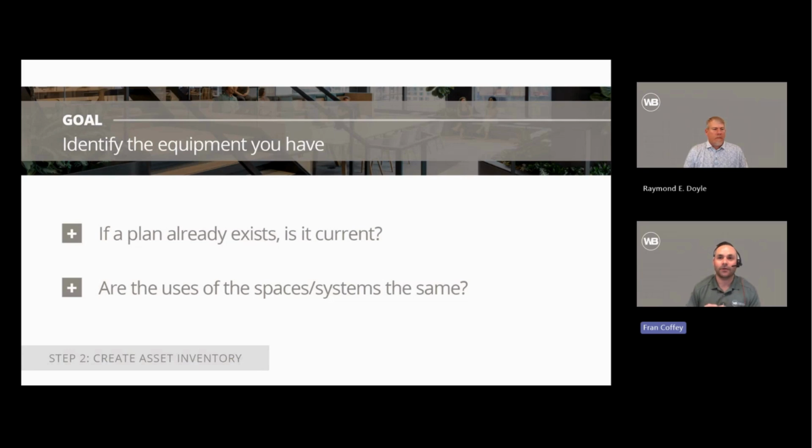You don't want to have a 100% outside air, 2N redundancy system serving an office space just because that's what the space served before. So it's really crucial to understand how the space is set up, what the systems are, how they differ, and how you can have common systems serve both spaces, and make sure that you're not doing overkill just because that's what's in place.